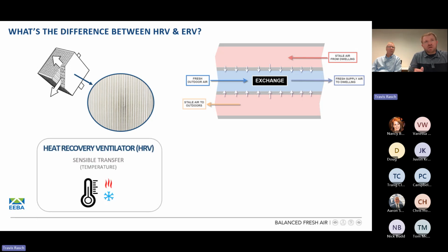There are two types when it comes to these recovery ventilators. The first is the HRV. This is a technology that's been around since the late 70s, early 80s. It started up in Saskatchewan, Canada, and has since obviously proliferated. We have been using them for quite some time now throughout the North American market. With an HRV, or heat recovery ventilator, we're simply moving a sensible transfer: temperature, hot going to cold. As you see in that upper right cross section, again, we've got cold air coming in, and we've got that stale, polluted air getting pulled from the house that's warmer. We're going to warm up that outdoor air in this situation with an HRV.